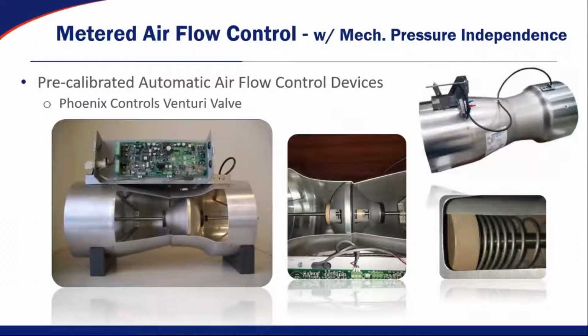Phoenix Controls valves work largely on the same principle. So if you see the pictures on the bottom right-hand corner, you can see there is actually a calibrated spring inside the cone in the middle of the Phoenix Controls valve, and that is what allows the valve to be pressure independent mechanically. It also gives us the high turn down ratio and the flexibility of the airflow control situations that we play in.